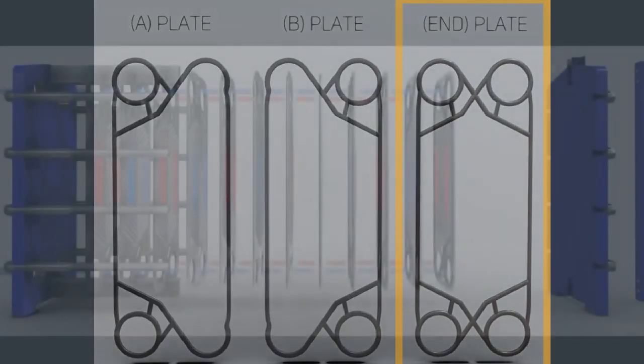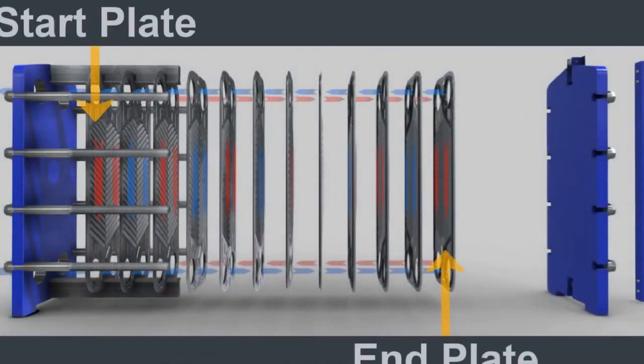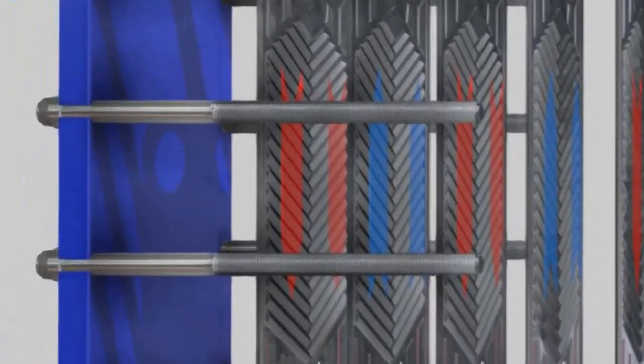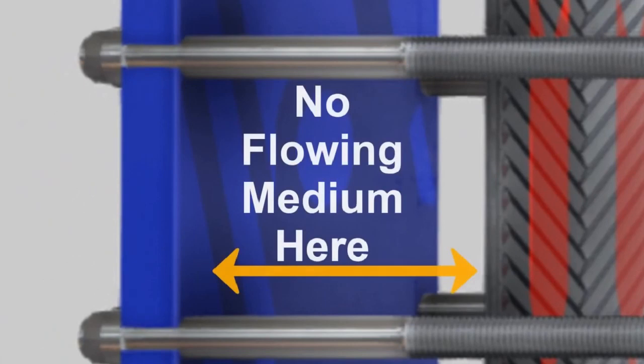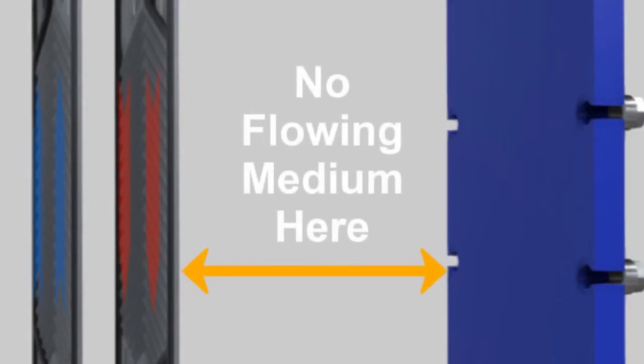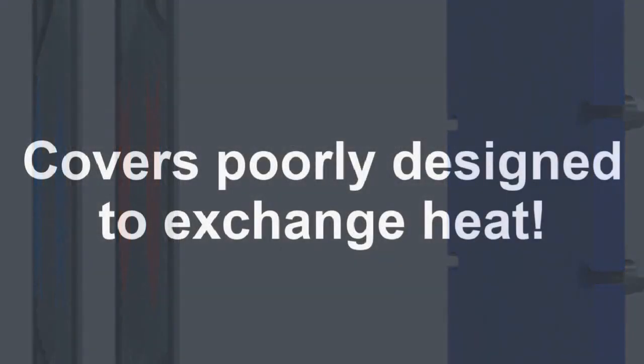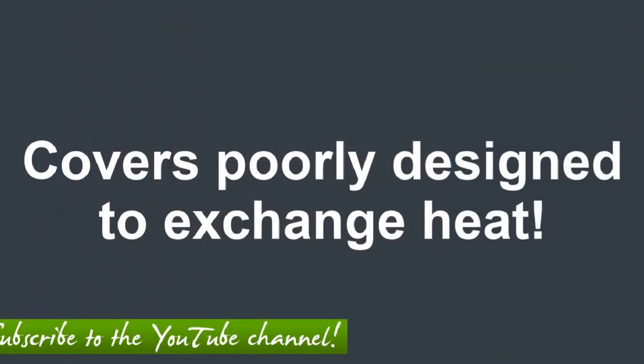Plates that press against the fixed and movable covers are known as start and end plates, because of their position within the plate stack. The purpose of the start and end plates is to prevent flow into the space between the fixed cover and start plate, and to prevent flow into the space between the movable cover and end plate. In this way, the covers are not actively used to exchange heat. This makes sense because each of the covers is quite thick, there are no corrugations, and they're poorly designed to exchange heat.